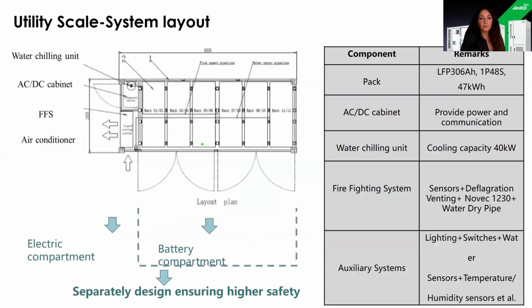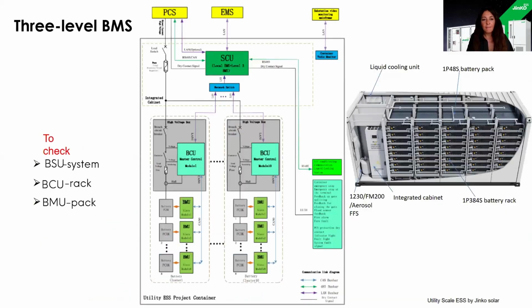Next slide, please. Here it shows that we really differentiate the battery compartment from the electric compartment, so as not to disturb the activity of each device. In the electric compartment are the air conditioner, the firefighting system, the water chilling unit, and the AC/DC cabinet providing internal power to the battery. The battery part contains all 12 racks, for the whole 5 megawatt-hour solution.